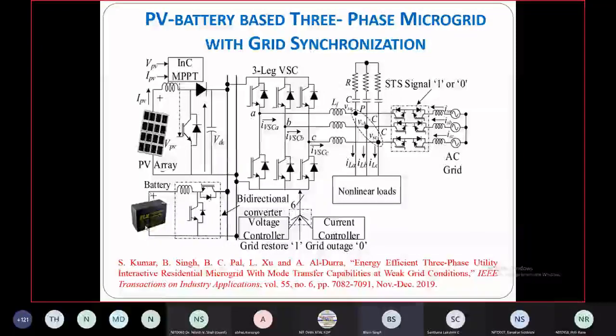One benefit is that now the battery voltage rating can be decided according to battery capacity. It need not be the same as the DC link voltage. Another benefit is that because you are controlling these two switches either for charging or for discharging, you can control the battery current with no lower order harmonics like the second harmonic. Because in this case, second harmonic will be there on the DC link, because that is the nature of the system, either you have an unbalance in the voltage or an unbalance in the current.